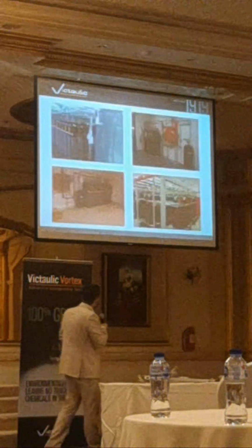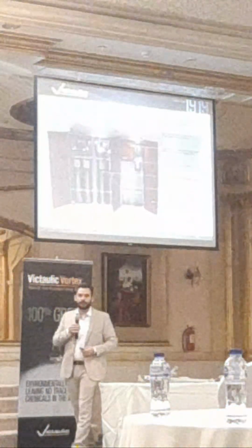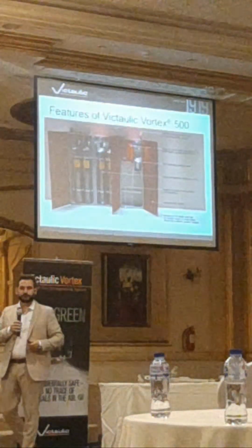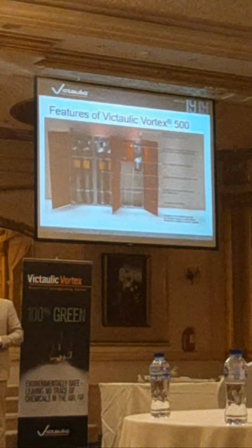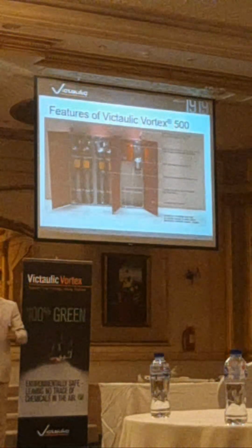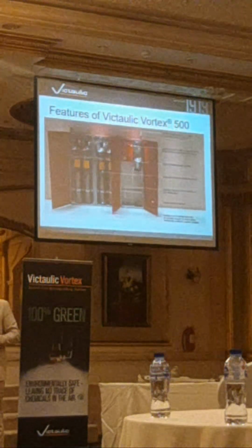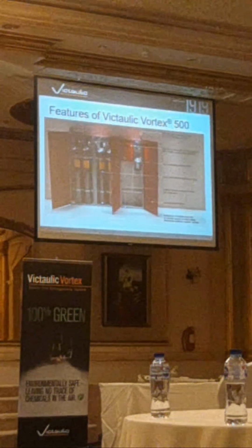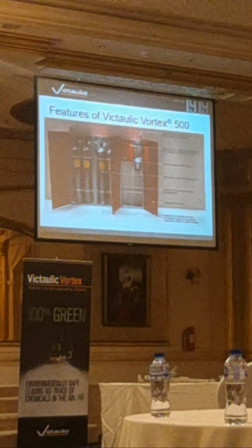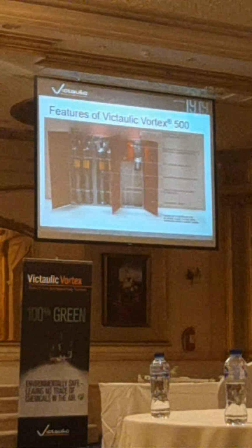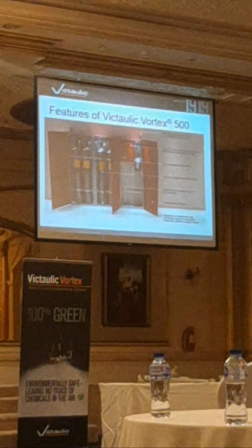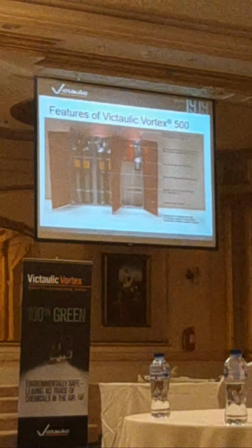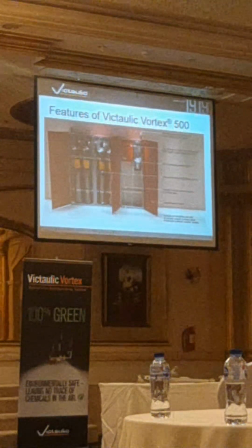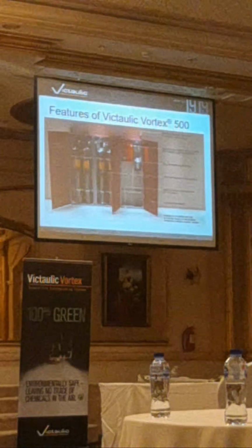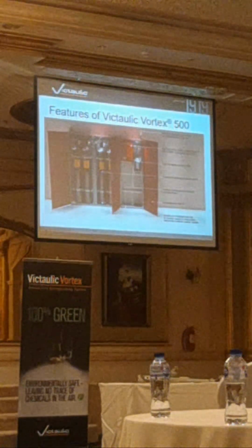Excuse me. Yes. Extinguishing duration for this system, how many minutes? The activation of the system? Yes, for how many minutes? The activation will depend a little bit on the detection. No, I'm talking about you decide a certain water tank, right? Yeah. Your system will work to extinguish the fire for how many minutes? 3 minutes discharge in total. How much? 3 minutes in total. Only 3 minutes? Yes. The approval is for 3 minutes only? Correct. Because you're adding the gas as well. For a certain hazard? For data processing equipment and Class B.